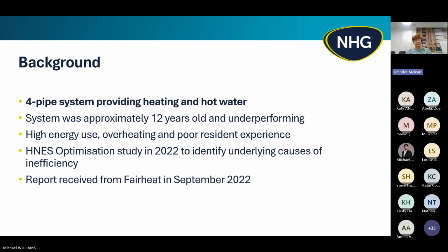In terms of background, the site was approximately 12 years old when we started noticing system underperformance issues, primarily high energy use, very significant overheating, and poor resident experience. It was a 4-pipe system providing heating and hot water, like many communal heating systems built at that time.